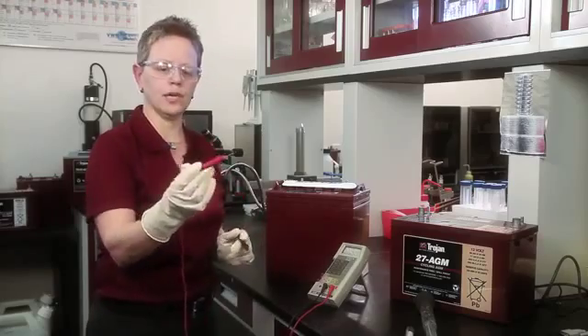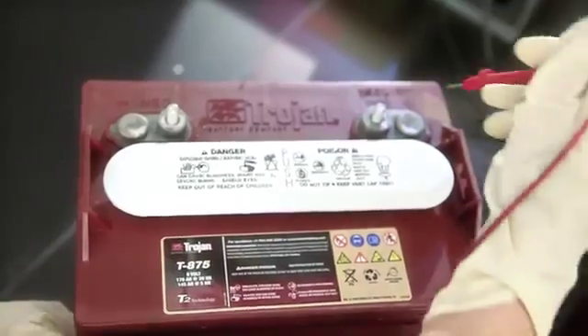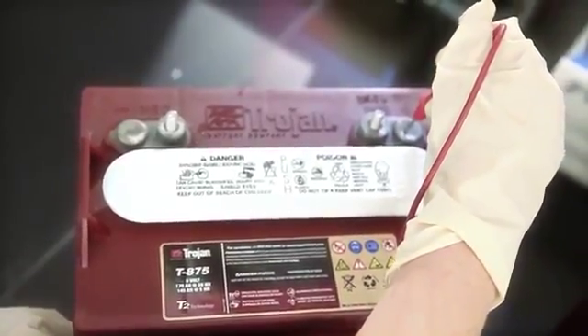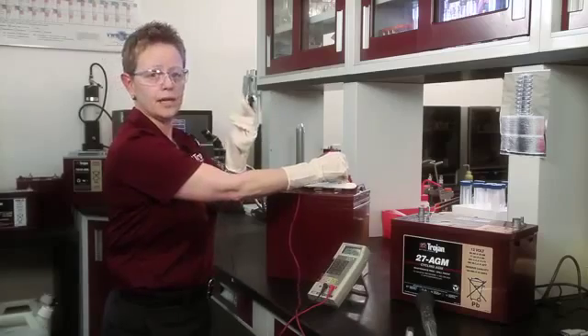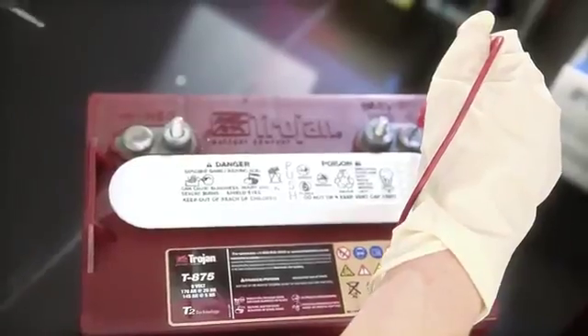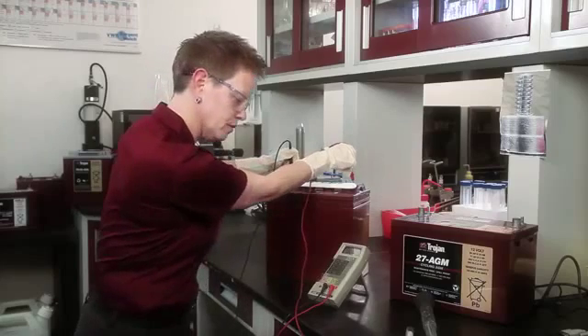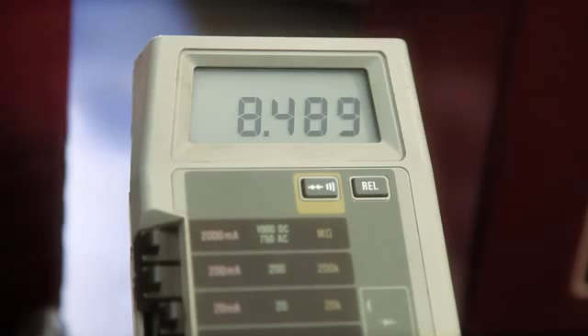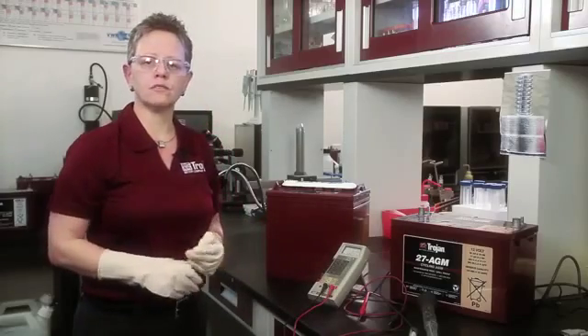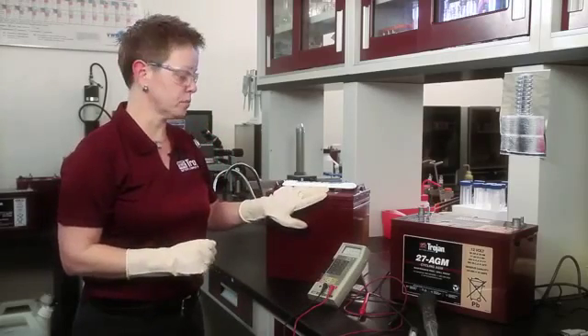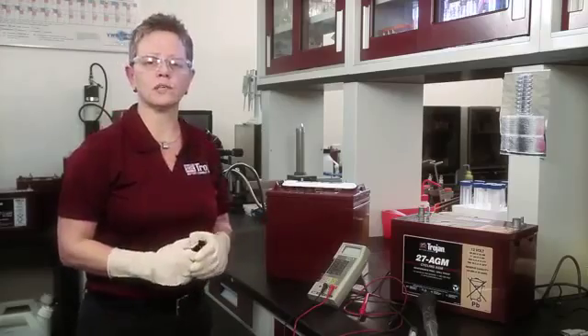And all you do is you take the positive probe from the voltmeter, connect it to the positive terminal on the battery. You take the negative probe, which is black, and connect it to the negative terminal on the battery. And you read the voltage, 8.48, which is an acceptable voltage. The next thing that you do to read the state of charge of a flooded battery particularly would be to read the specific gravity.